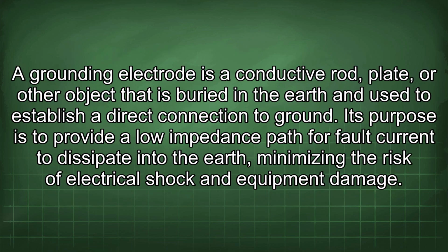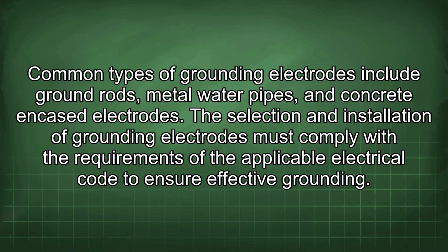A grounding electrode is a conductive rod, plate, or other object that is buried in the earth and used to establish a direct connection to ground. Its purpose is to provide a low-impedance path for fault current to dissipate into the earth, minimizing the risk of electrical shock and equipment damage. Common types of grounding electrodes include ground rods, metal water pipes, and concrete encased electrodes.